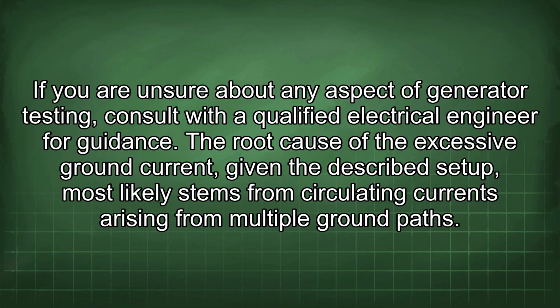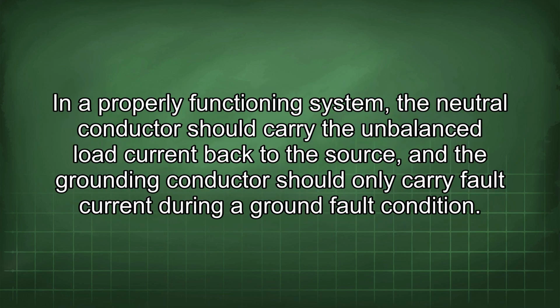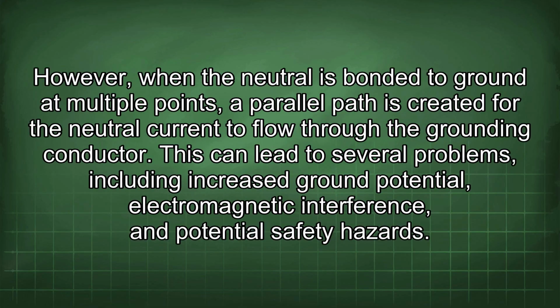The root cause of the excessive ground current, given the described setup, most likely stems from circulating currents arising from multiple ground paths. In a properly functioning system, the neutral conductor should carry the unbalanced load current back to the source, and the grounding conductor should only carry fault current during a ground fault condition. However, when the neutral is bonded to ground at multiple points, a parallel path is created for the neutral current to flow through the grounding conductor. This can lead to several problems, including increased ground potential, electromagnetic interference, and potential safety hazards.